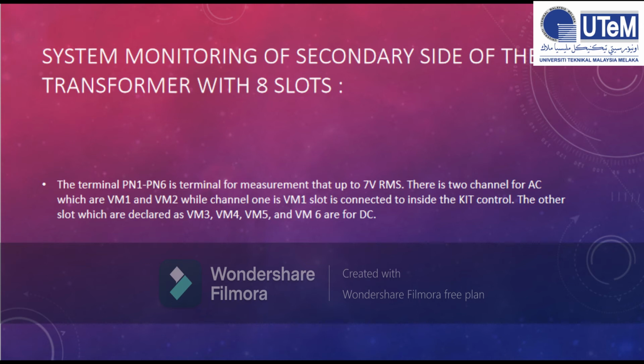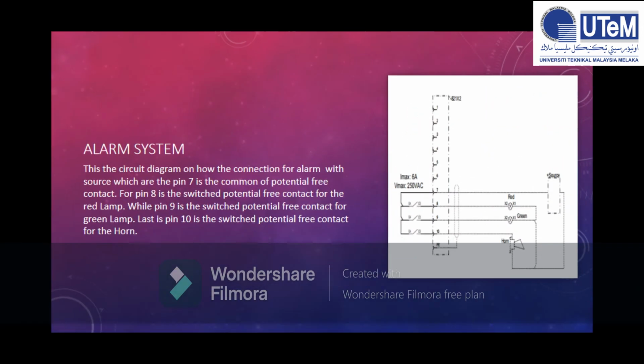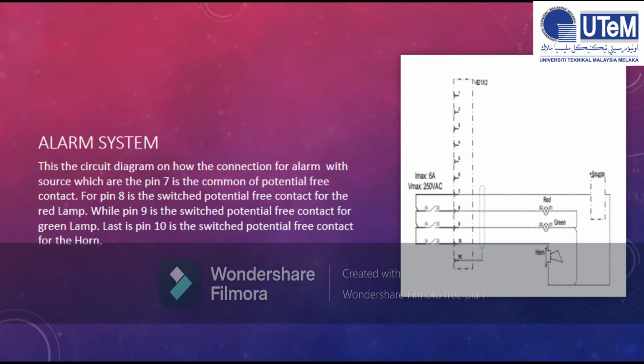Next is alarm system. This is the circuit of alarm system. On how the connection for alarm with source, which the pin 7 is the common of potential free contact. For pin 8 is the switch potential free contact for the red lamp, while pin 9 is the switch potential free contact for green lamp. Last is pin 10 is the switch potential free contact for horn.